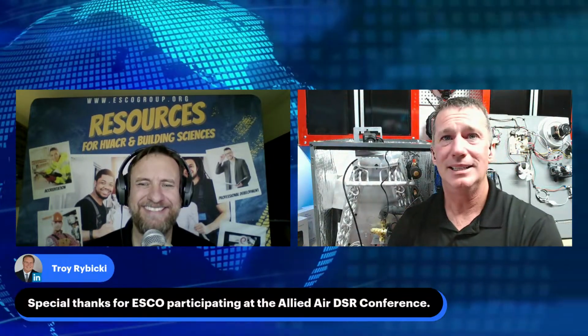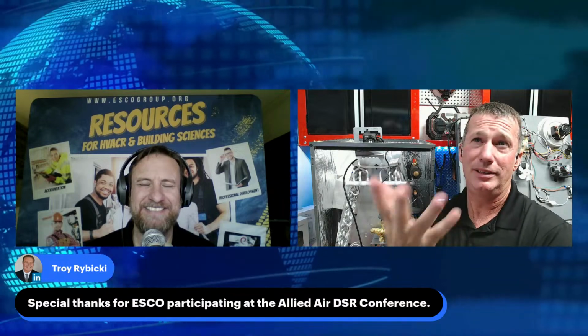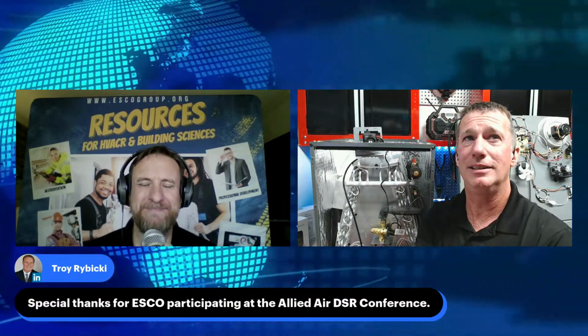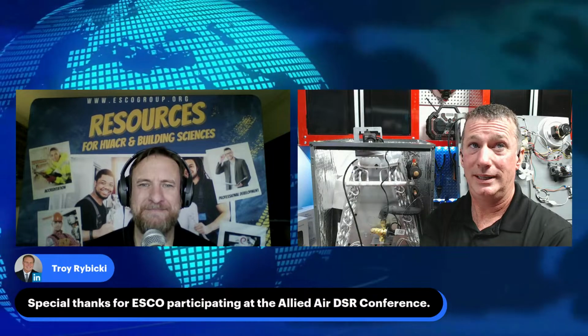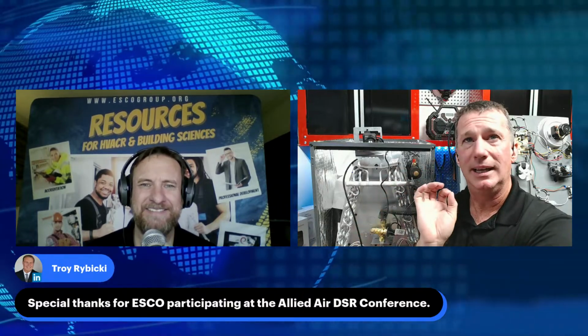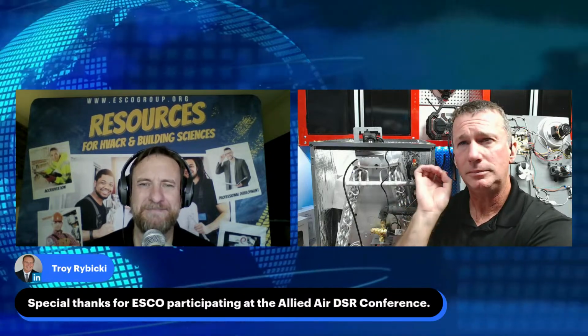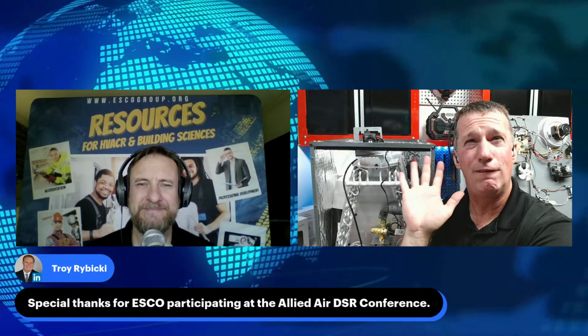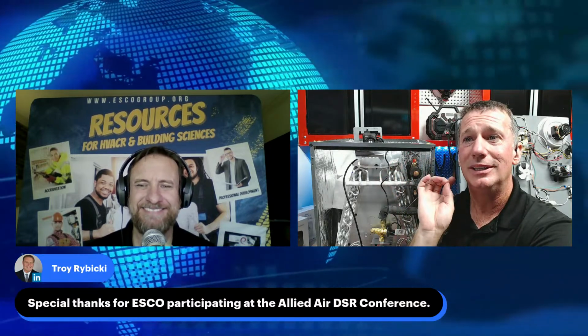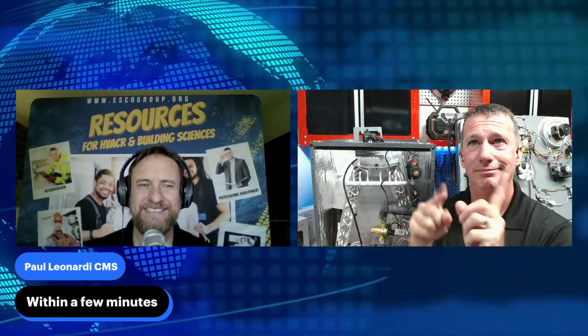So this was one of the questions I asked in class quite often, asking people what they thought. And Ty, if we think about a gas appliance, how long does it typically take for that thing to initiate a state of soft lockout? Pretty quick, right? Okay. So with this particular sensor and this particular control, it actually does sampling every 5 seconds. And if it reaches the lower flammability limit, it will go into a state of soft lockout for 5 minutes. And it will initiate, within a few minutes, Paul. Exactly right. It's actually going to be, should be, hopefully, within a 5-second period.